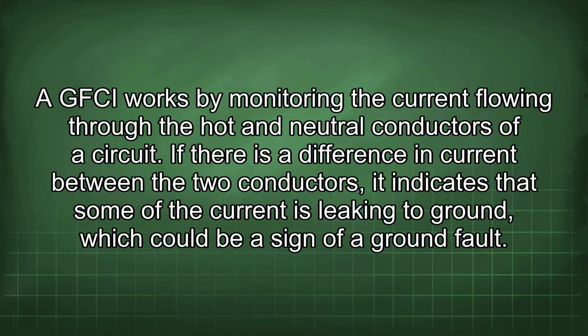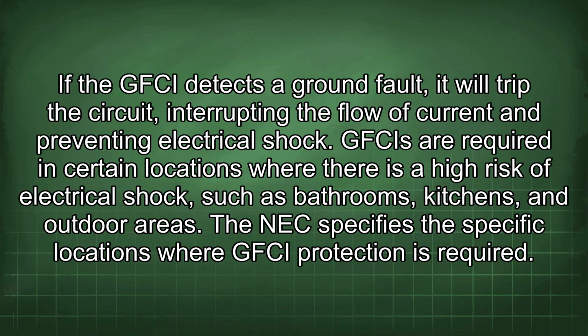A GFCI works by monitoring the current flowing through the hot and neutral conductors of a circuit. If there is a difference in current between the two conductors, it indicates that some of the current is leaking to ground, which could be a sign of a ground fault. If the GFCI detects a ground fault, it will trip the circuit, interrupting the flow of current and preventing electrical shock. GFCIs are required in certain locations where there is a high risk of electrical shock, such as bathrooms, kitchens, and outdoor areas. The NEC specifies the specific locations where GFCI protection is required.